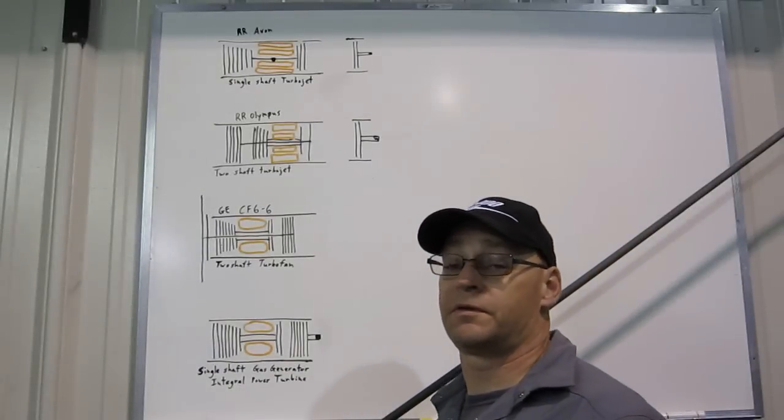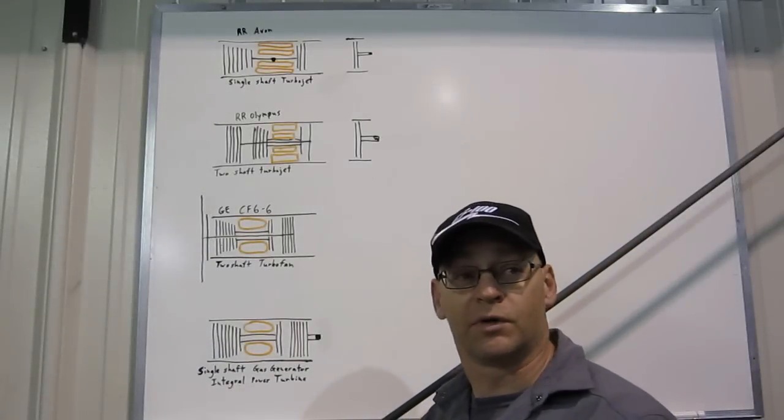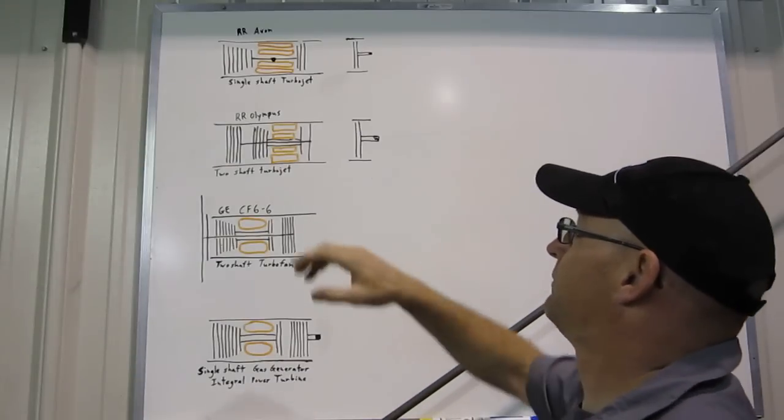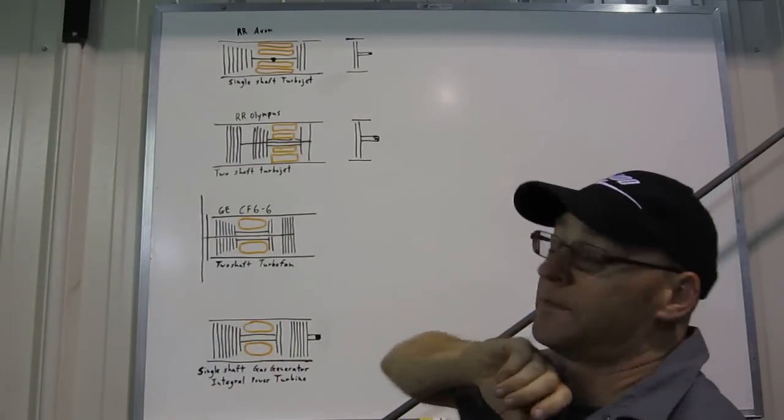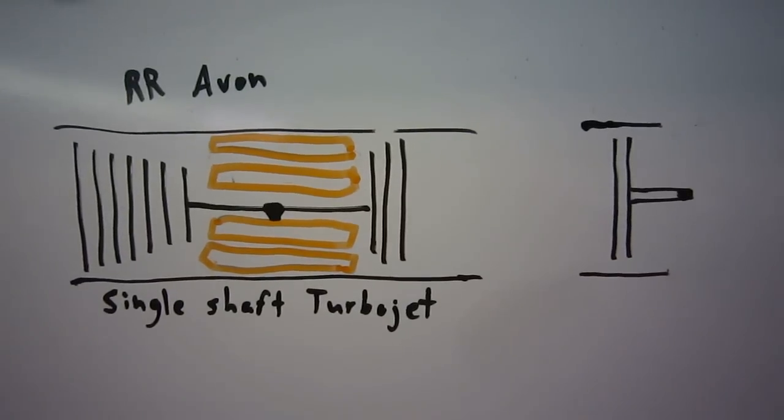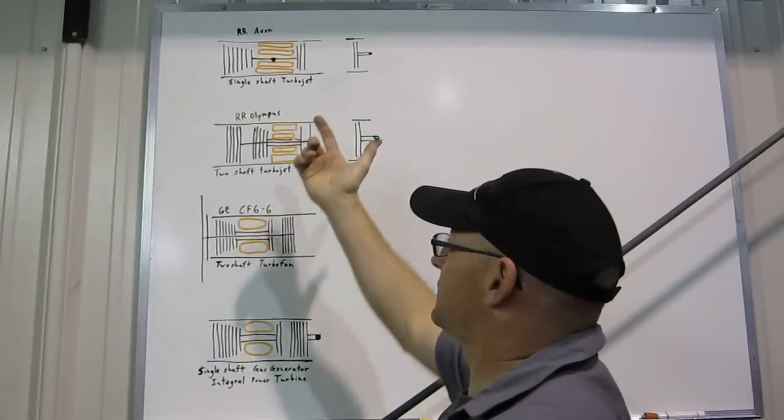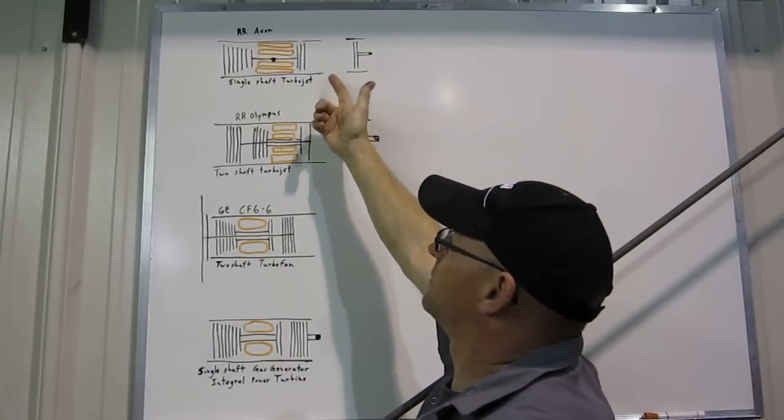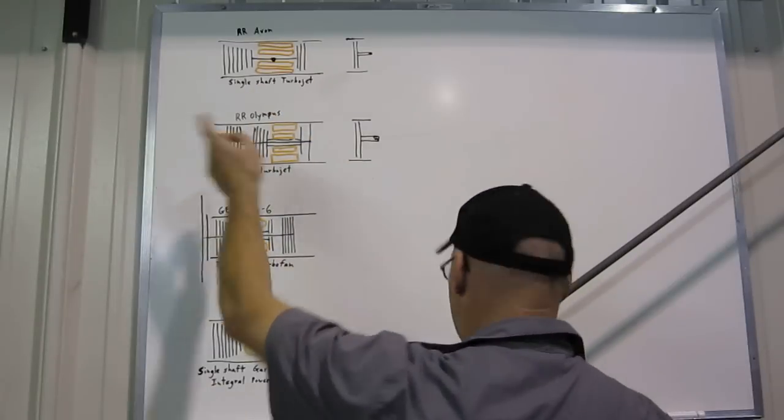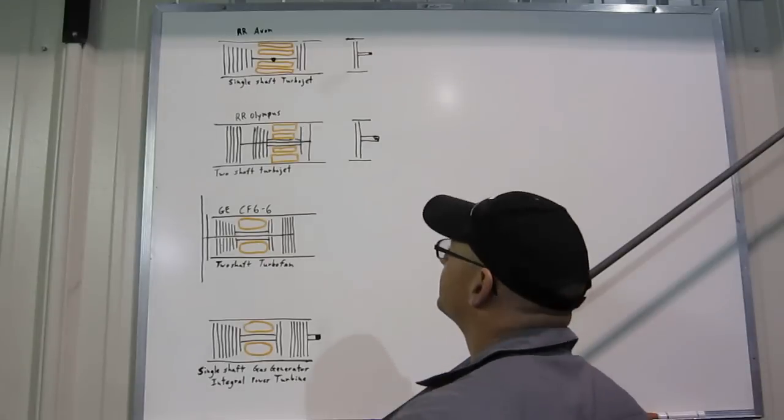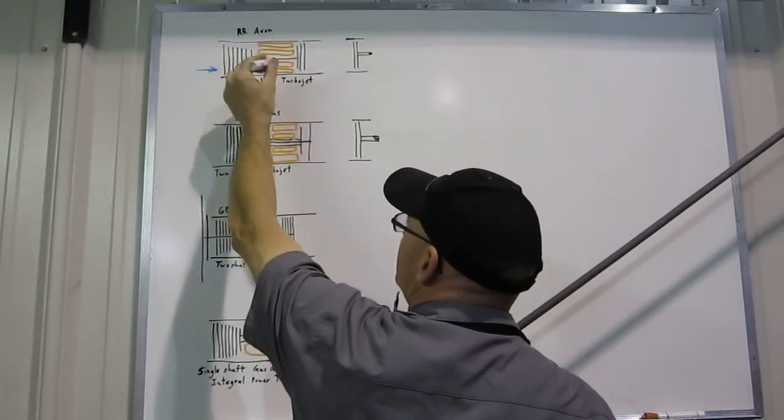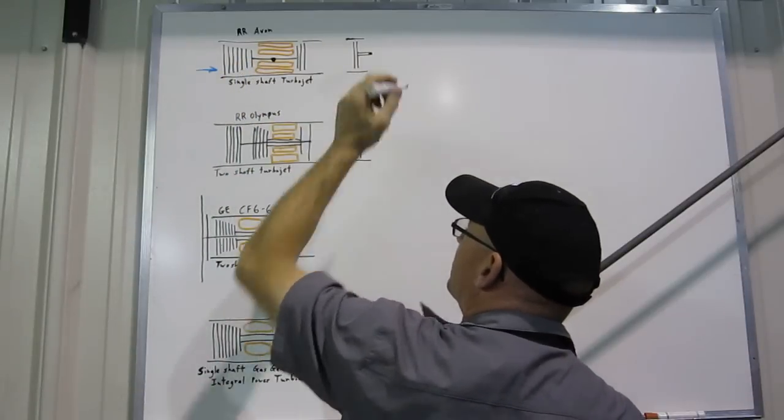Okay, a couple more diagrams to further explain some of the more subtle differences. I've drawn on the top our typical industrial engine, which is a single spool gas generator. It's basically a turbojet engine minus the nozzle, and I've included the power turbine. All of the air going in goes through the entire engine, is combusted with the fuel and comes out the back through the power turbine.